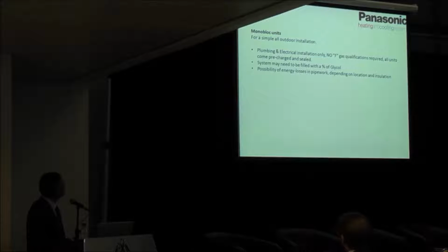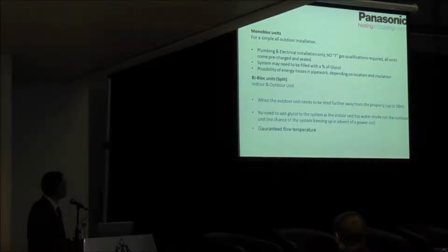So where would we use monoblock units? The advantages of using monoblock is there's no refrigeration pipework required. So you don't have to worry about any F-gas regulations. It can be installed by any reputable installer. But because we've got water in the outside system, you may need to look at adding glycol. You also need to look at the distances between the outdoor unit and the indoor unit, because you may have losses in thermal capacity. So you need to make sure that the insulation that you utilise is of a high standard. With bi-block or split systems, we have the outdoor unit, we have the indoor unit, and we have refrigeration pipework in between the two. So essentially, they can be piped up to 30 metres away. You have no need to add glycol to the system, and you're guaranteed your flow temperatures.